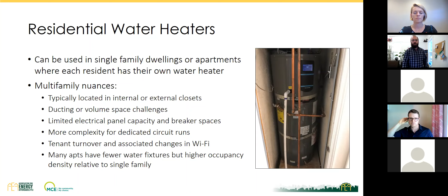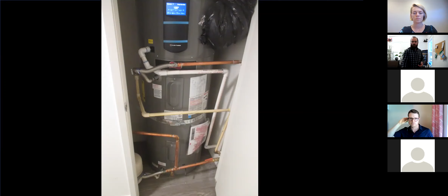These are some examples of single-family-flavored heat pump installations. Here is a ducted one in an exterior closet. This is a ducted combination system in an interior closet. One of the things to note in these pictures is that there is ducting leading out of the systems. This is because cold air is a byproduct of heating the water, and in enclosed spaces such as a water heater closet, that cold air needs a way to exit. Otherwise, the system efficiency can be dramatically reduced as the air that's being exchanged and heat extracted from gets colder. So make sure you refer to the manufacturer's specs for information on ducting and fresh air exchange requirements.